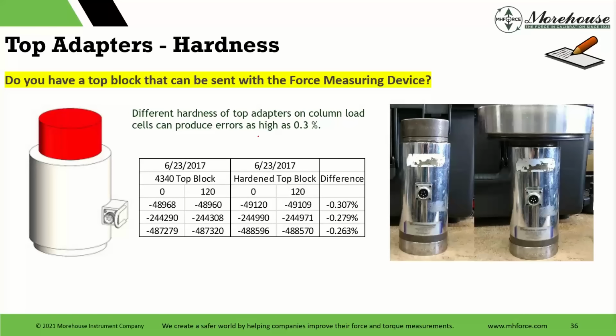Top block and hardness. The reason I talk about this is we started with the hardness of materials, but if we look at this, it's just two calibrations, right? One setup here on the right and one setup on the left. These numbers are coming from the different hardness of the top adapter, and there's a radical change in the amount of deflection depending on the hardness. And we're going to get to why this could be a safety issue. There's a lot of things that can go wrong here with top adapters. If engineers do not design and make the appropriate top adapter with the proper size and thickness, and we apply too much force, it will crack.